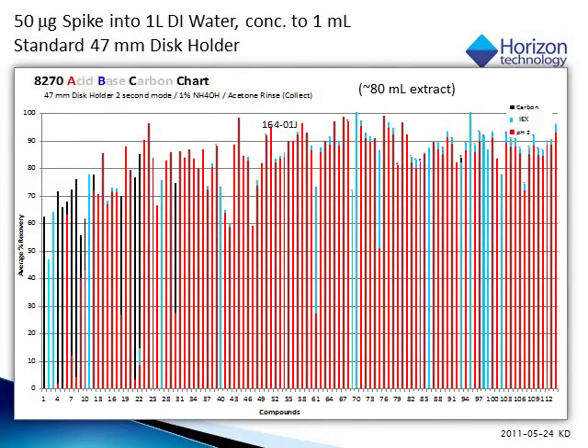Here is the recovery chart from the demonstration sample. The compounds are shown by elution order off the GC. The acids and neutrals are depicted by the red bars, the compounds captured by the carbon cartridge are shown in black, while the blue bars are the organic bases. Overall recoveries are excellent, and light ends are captured exceedingly well compared to liquid-liquid extraction, including the phenols.